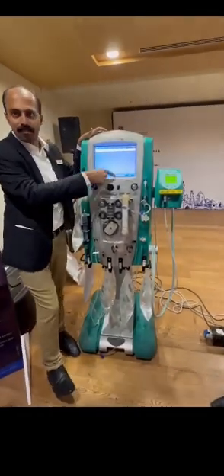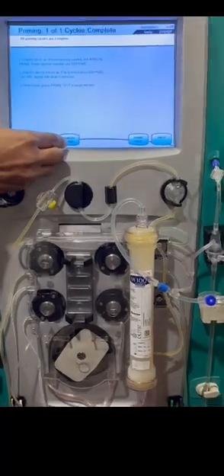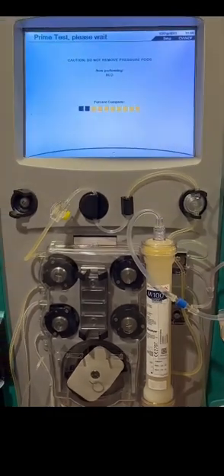Now this priming is completed, I will tell you. Now we will go for the test, the prime test. Still we have two options, reprime or manual prime if required. But now this is fine, there is no error, so we can go for the prime test.